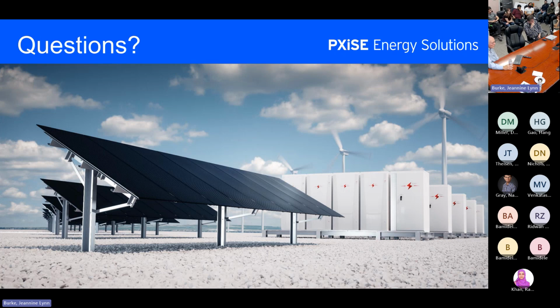So you mentioned something about islanding, and I think right now most of the protection companies, when there is a fault and you want to disconnect at the POI, think that the fastest protection element they have right now is the fast DFDT, the fast ROCOF. But in the case where the import is low, the fast ROCOF or the fast DFDT would not actually do the work of opening the breaker at the POI.